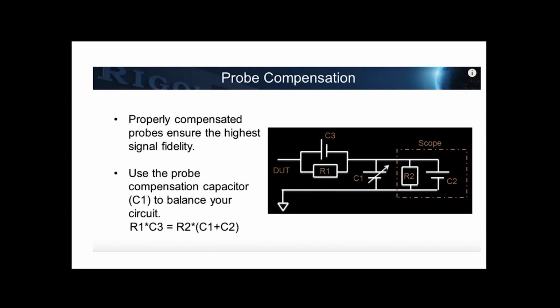A lot of modern scopes, you can tell them that you're using a 10-to-1 probe, and it'll actually do the conversion for you. It'll add the 0 on. But failing that, if you've got an older scope, you maybe have to remember to add a 0 on. And so if you're using a scope probe, you have to calibrate it, and you have to remember that it's a 10-to-1 scope probe. Some scope probes have got a switch on them, 10-to-1 or straight through. If you go straight through, then you lose the trimming of the trimming capacitor to make your scope probe linear, but you do gain the fact that the voltage at the scope is the voltage at the device under test.